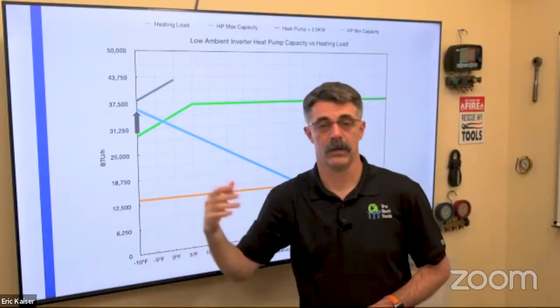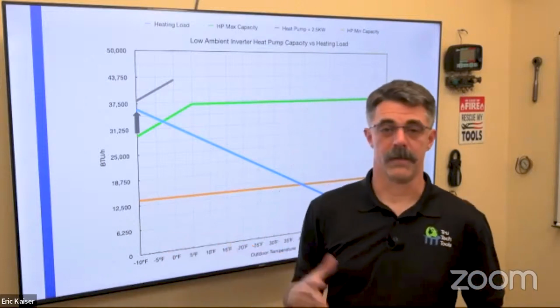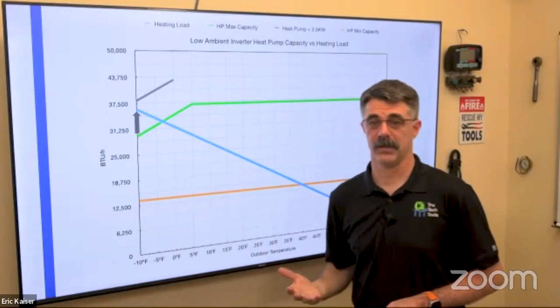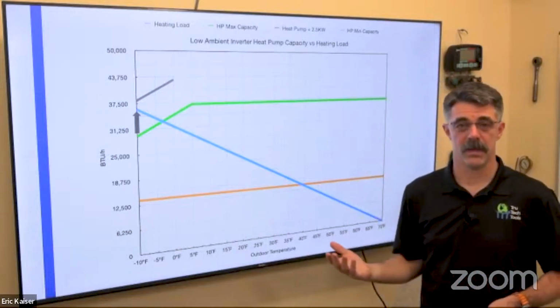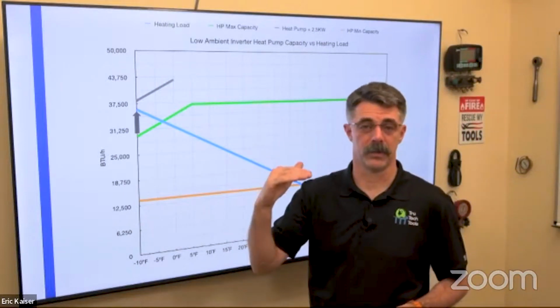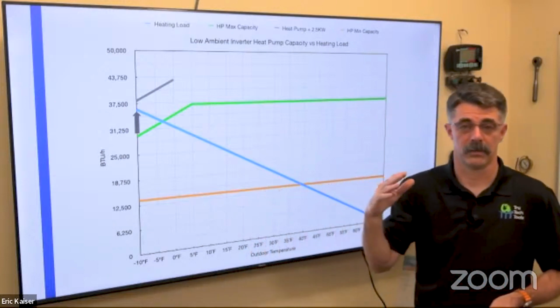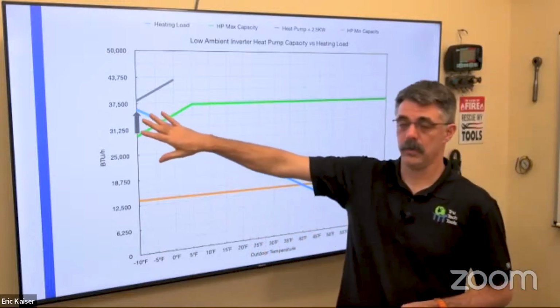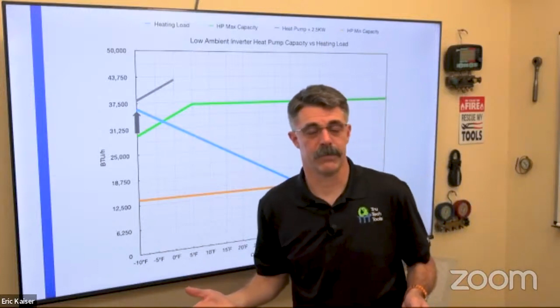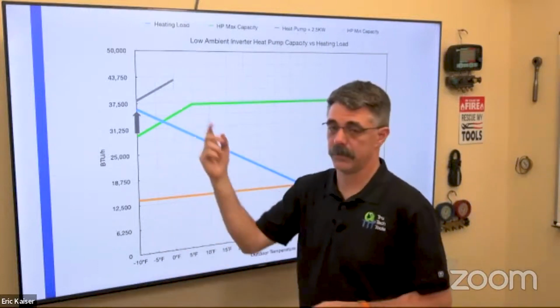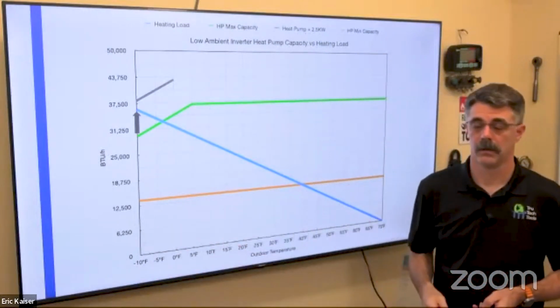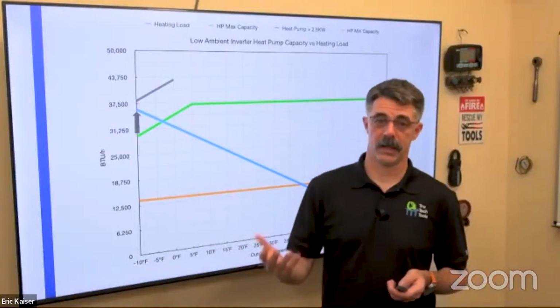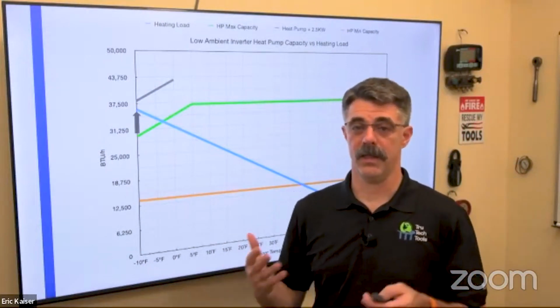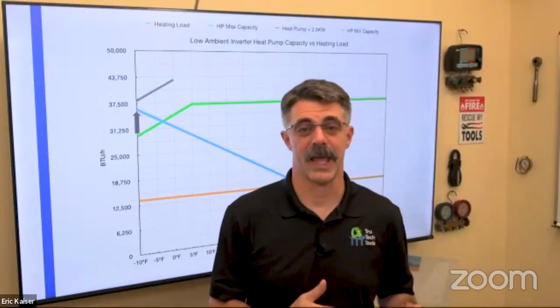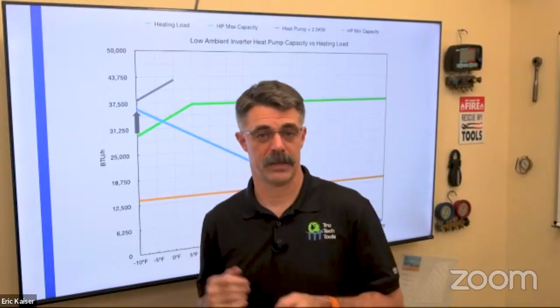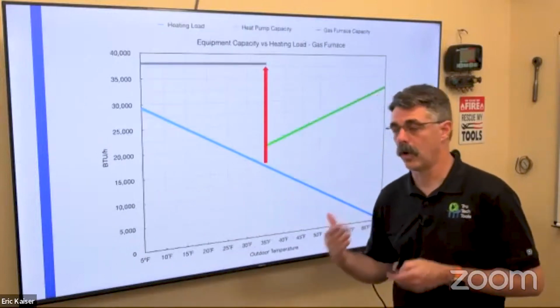are you okay if it goes down below zero, if your house temperature drops just a little bit? It's not going to go freezing, but maybe if they keep it set at 70, it might droop to 68 or 66, something like that. They may lose just a little bit. Okay, fine. If they're happy with that, you don't have to turn that electric heat on. Okay, so different options, understanding what your customer's comfort level is, then understanding what the equipment is capable of, and then how to set that up. Those are all parts of this.